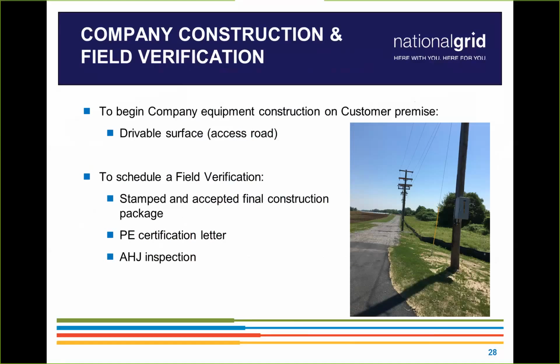And then from there, once we complete our construction and the customer completes his construction, our engineers can go out and do a field verification and inspect the installation to determine if it conforms with the accepted design. Then the customer can provide the certification letter, which really states that the installation in the field has met all the requirements based on the approved design. And from there, once we get the electrical inspection, we can start moving on to witness testing. And before I move into witness testing, Chris, is there anything else you want to say?